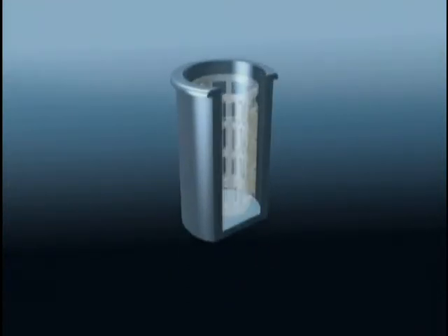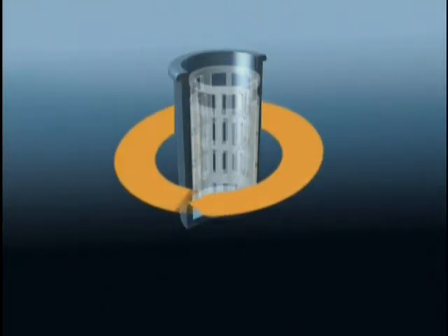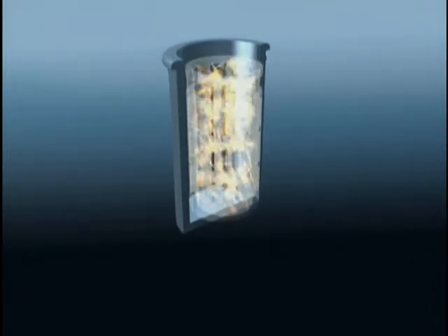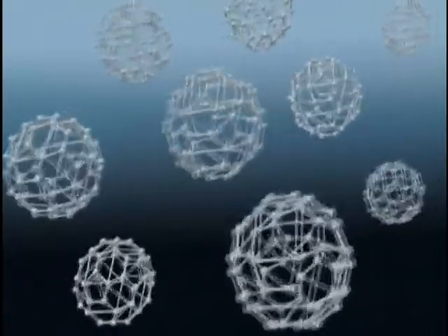Express microwaves are initiated when a basket is lowered into position inside the retort. The shape, dimensions, and material used in the retort cavity enhance the activity of the Express microwaves during each processing step. The waves circle the cavity and take advantage of a physical principle known as the whispering gallery effect, which makes it possible for biopsy and routine specimens to be processed in the same run. The use of very low power enables constant, gentle energy distribution. Molecules in the tissue being processed in the Express react to the microwaves, moving in a consistent manner, resulting in uniform heating throughout the tissue. In contrast, standard microwaves using such high wattages can cause erratic molecular activity, causing uneven heating and more variable results. The Express also enhances processing by injecting air bubbles from the bottom of the basket, ensuring temperature distribution for optimal processing.